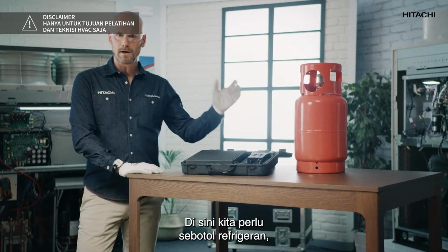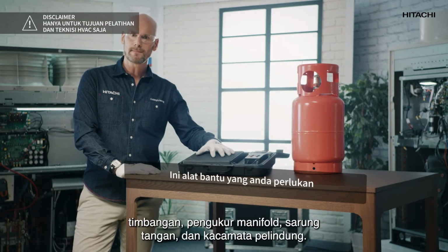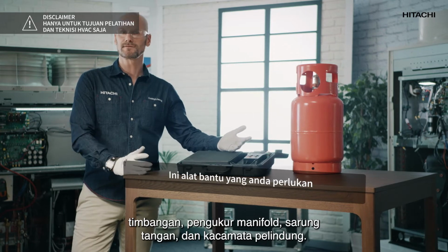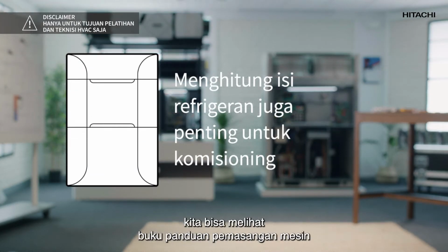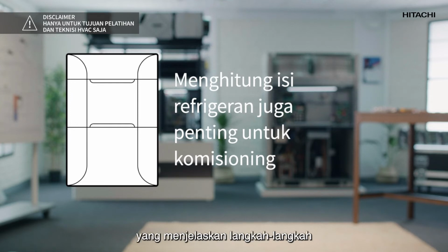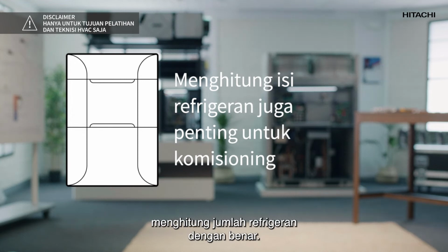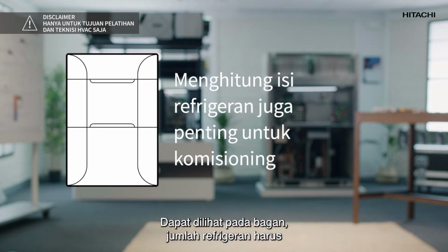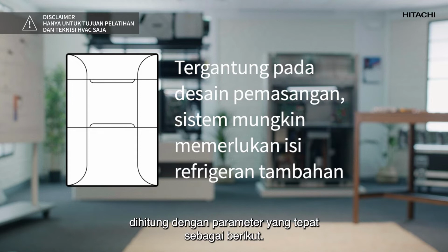For this, we will need a bottle of refrigerant, a scale, a manifold gauge, gloves and goggles. To find out how much gas we have to charge, we should refer to the installation manual of the machine, where it explains the steps to follow to calculate the correct quantity of refrigerant. As you can see in the chart, the amount of refrigerant must be calculated using the following exact parameters.